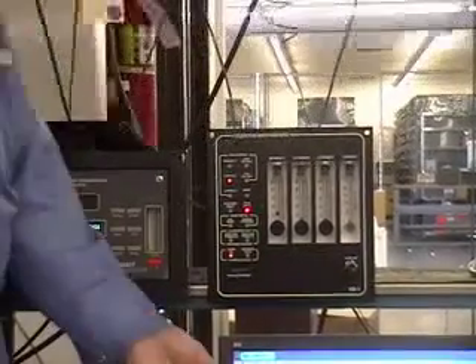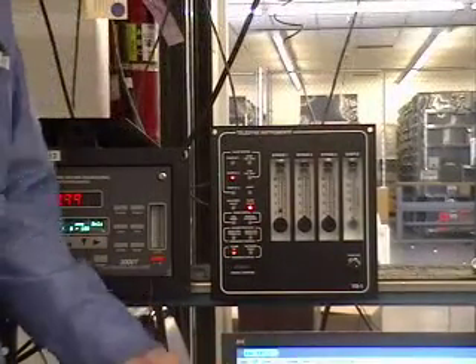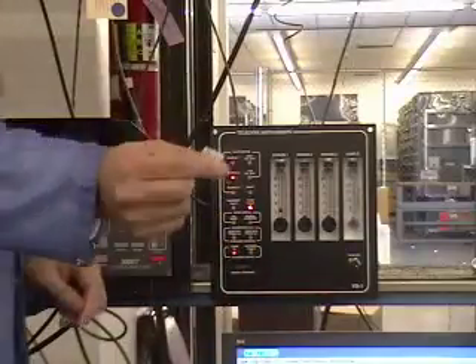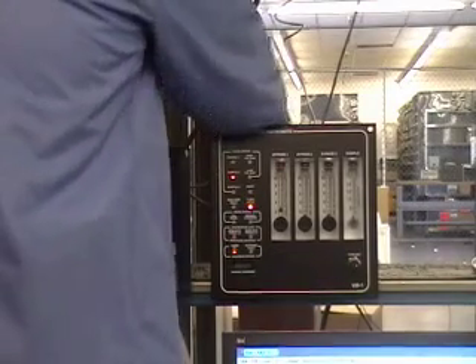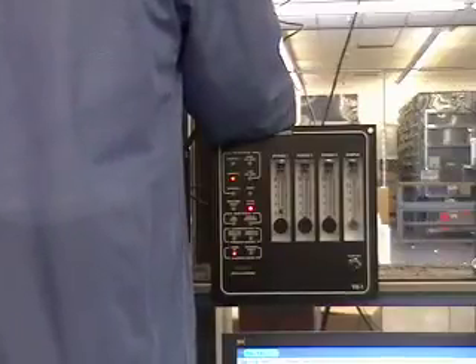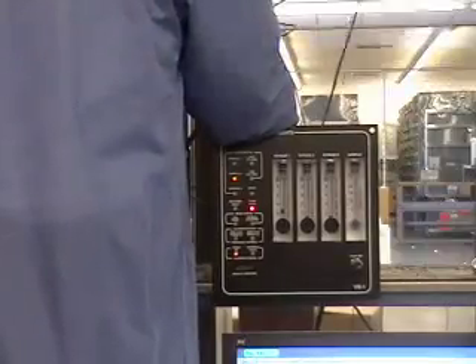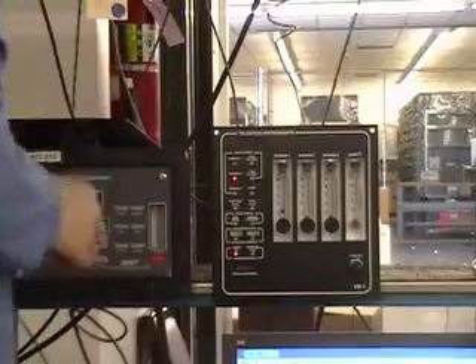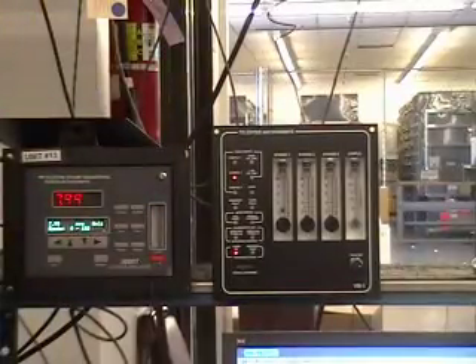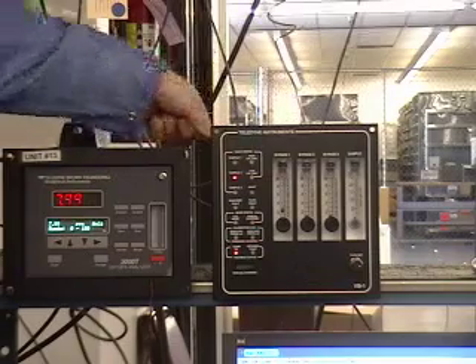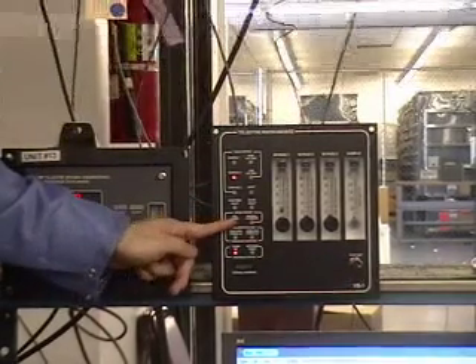But I am faking it right now because there is no gas flowing. So I'm faking it by putting a jumper across on the input. But if there was no gas flowing, that's what would happen. So now I'm going to fake it back that there is flow by shorting the terminal. Okay, so I reestablished flow. There is flow now. We are already seeing the cal mode in action. Whenever the analyzer is in zero mode or span mode, we see the cal light come on.